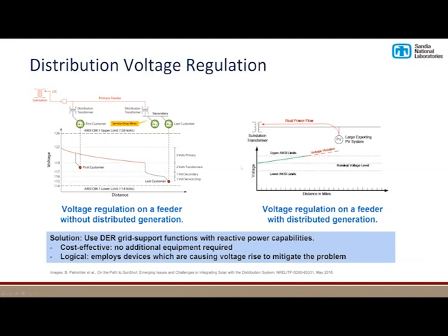And there are a couple of limits that utilities have to abide by. These are the ANSI range A and B limits associated with that voltage band. They need to operate within this to not damage equipment and to provide a good service to their customers. The question is, we can potentially add some additional equipment to this system as we install PV to correct for this problem, or the more cost-effective technique would be to use the capabilities of the inverters themselves to help bring down that voltage and control the voltage by communicating or using autonomous grid functions programmed in these devices. And so that's what we're trying to do here.